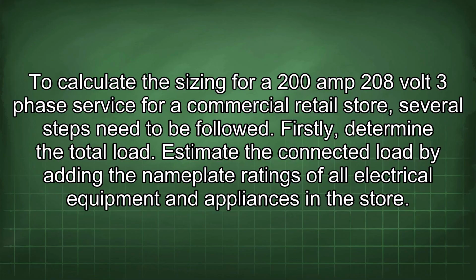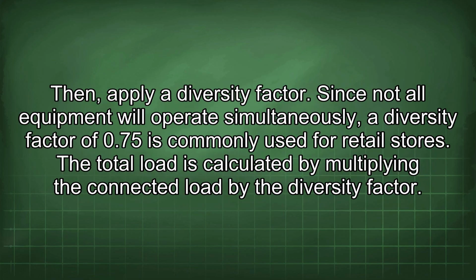To calculate the sizing for a 200 amp 208 volt 3-phase service for a commercial retail store, several steps need to be followed. Firstly, determine the total load. Estimate the connected load by adding the nameplate ratings of all the electrical equipment and appliances in the store. Then apply a diversity factor. Since not all equipment will operate simultaneously, a diversity factor of 0.75 is commonly used for retail stores. The total load is calculated by multiplying the connected load by the diversity factor.